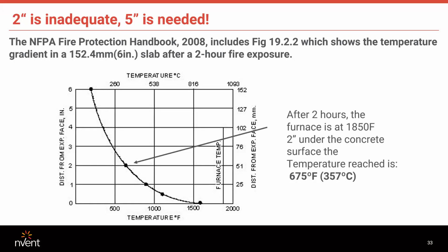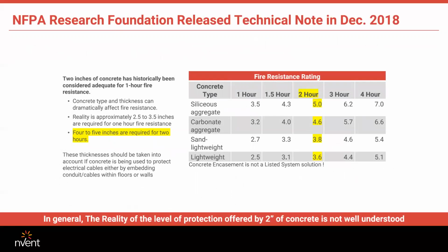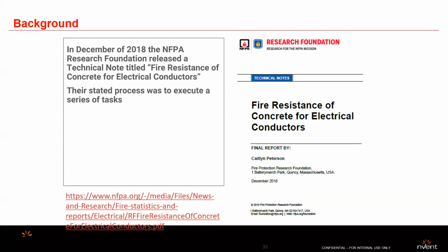That's more than 200 degrees hotter than what a circuit was shown to carbonize at when it wasn't protected. So 2 inches of concrete will not give you the requisite protection for a critical circuit. And in fact, NFPA just recently did some testing and a white paper on it, and they found that to basically achieve a 2-hour rating, you're going to need close to 5 inches of concrete, depending on which type is used. But siliceous aggregate, which I believe is what most construction sites use, you're looking at basically 5 inches of concrete.